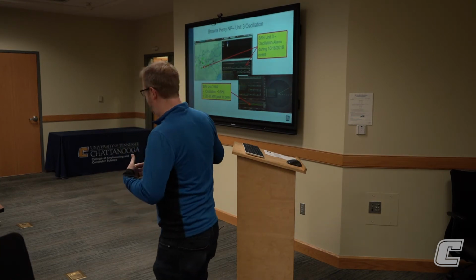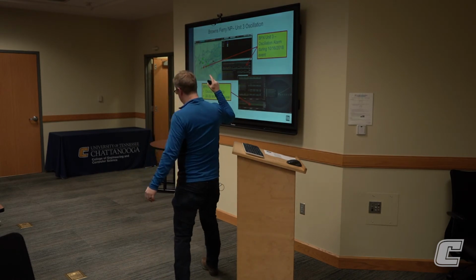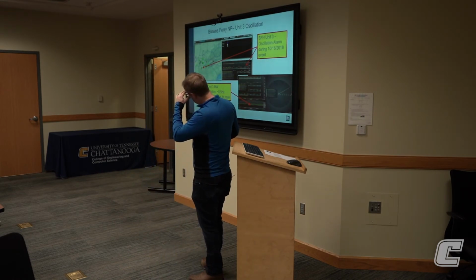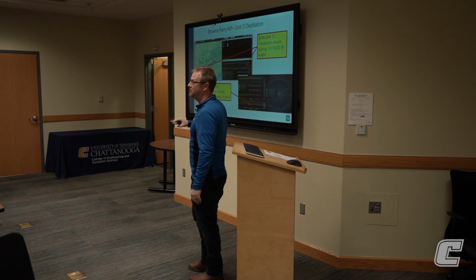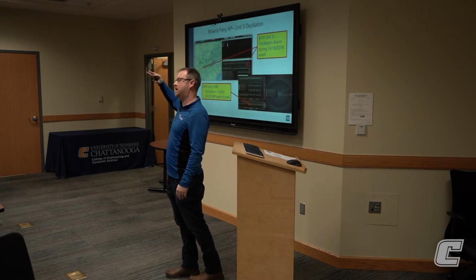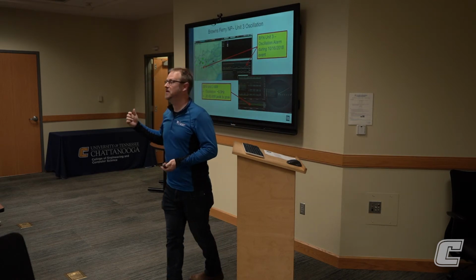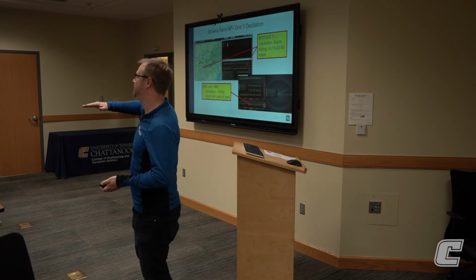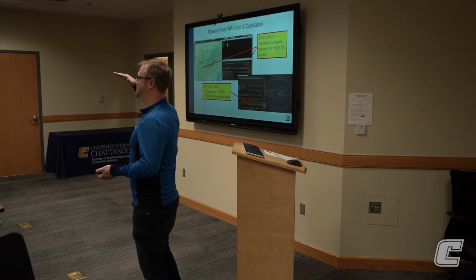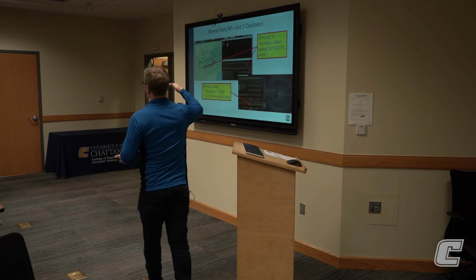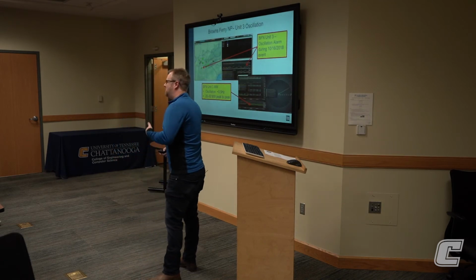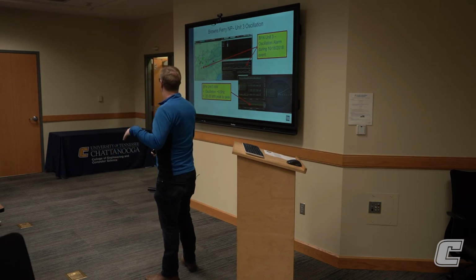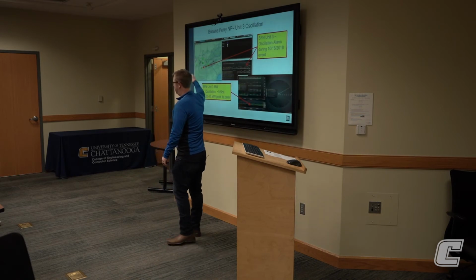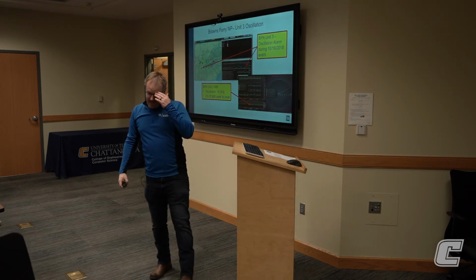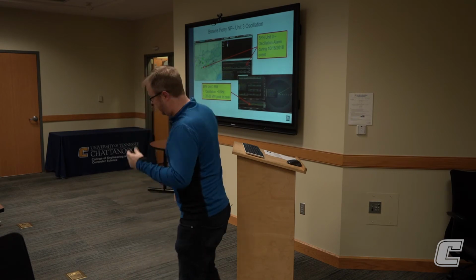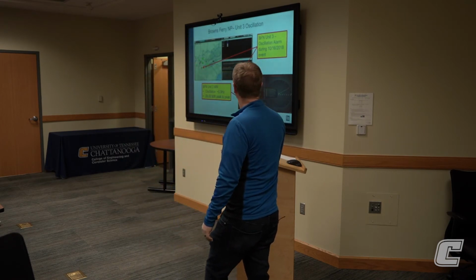They brought it back. We had a PMU there streaming synchrophasor data. Within, I don't know, a couple weeks after them bringing it up, they brought it up real slow. It's not like they just turned the switch on. It starts out at 0 megawatts and they would go up to 500 megawatts, let it sit for a week. Then they'd go up to 1,000 megawatts and let it sit for a week. And somewhere around 1,000, 1,100, we got an alarm for Unit 3. And, again, what's going on here?